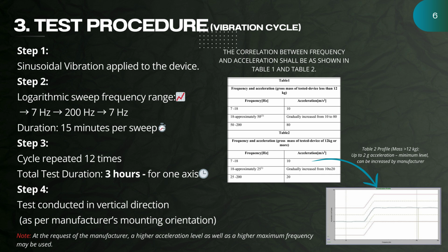Now, if you look at the tables on the right side, these show the correlation between frequency and acceleration levels. Table 1 and Table 2 specify the acceleration limits that must be met at each frequency band. Manufacturers may increase maximum acceleration levels if their product requires a more severe test. Moving to step 3, the complete sweep cycle is repeated 12 times, which gives us a total test duration of 3 hours for one axis.